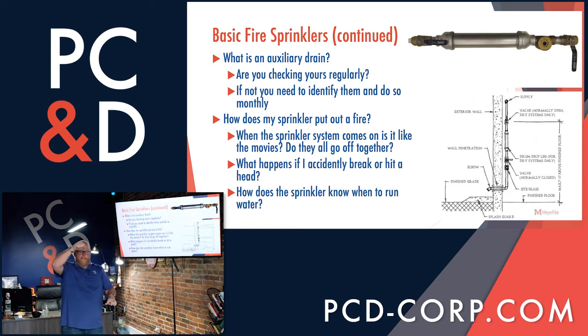Let the water run out of that point. Now you close your bottom valve, you open your top again. If there's still water above that top valve, you'll hear it trickling back down in. Give it a few seconds. Wait until you hear the trickling stop. Same steps again. Now I'm going to close the top, I'm going to open the bottom, I'm going to drain the water out. You may have to do that 3 or 4 times, especially if you're not familiar with the building and no one's done this in the past.